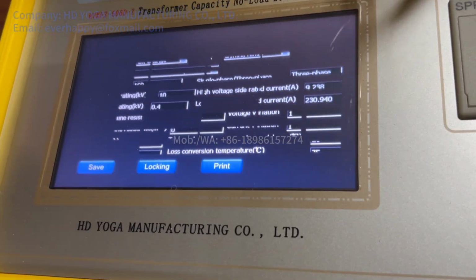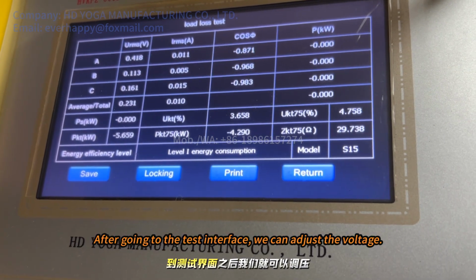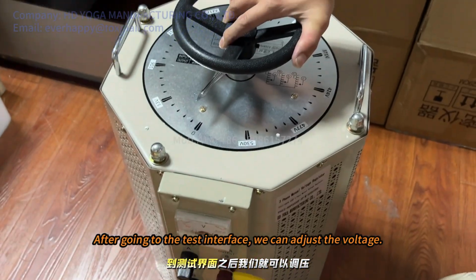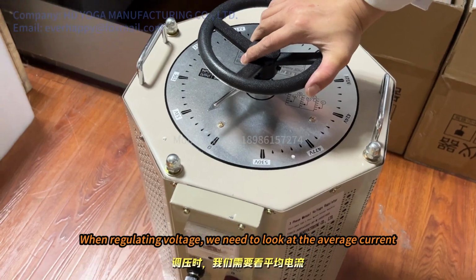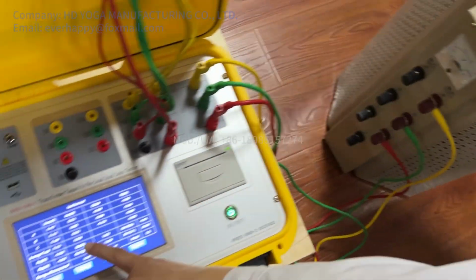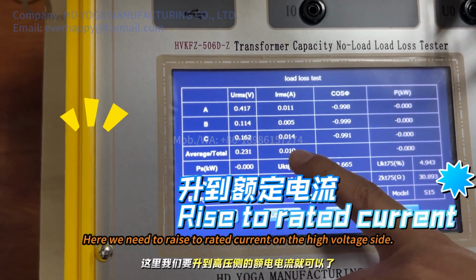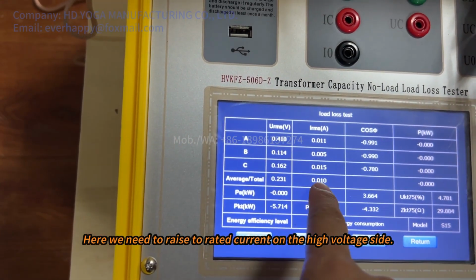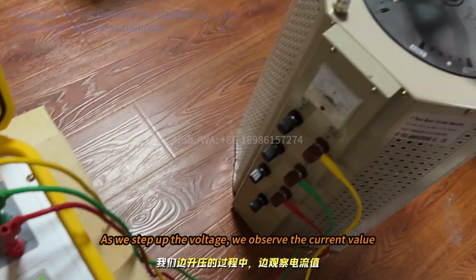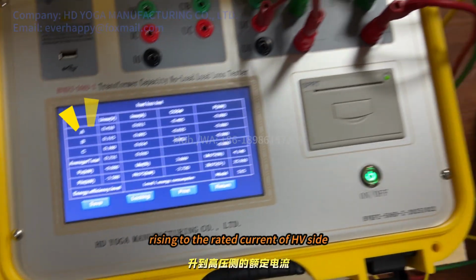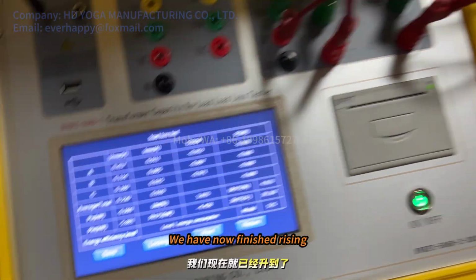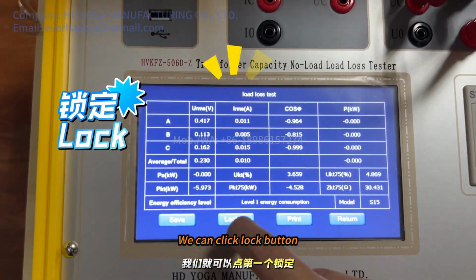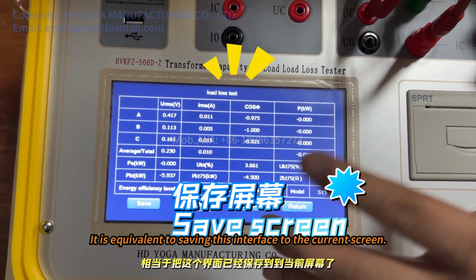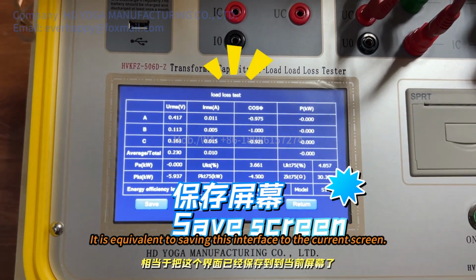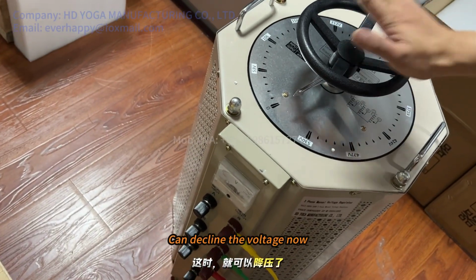After setting, we click OK. After going to the test interface, we can adjust the voltage. When regulating voltage, we need to look at the average current. Here we need to raise it to the rated current on the high voltage side. As we step up the voltage, we observe the current value rising to the rated current of the HV side. We have now finished rising. We can click the lock button. It is equivalent to saving this interface on the current screen. We can decrease the voltage now.